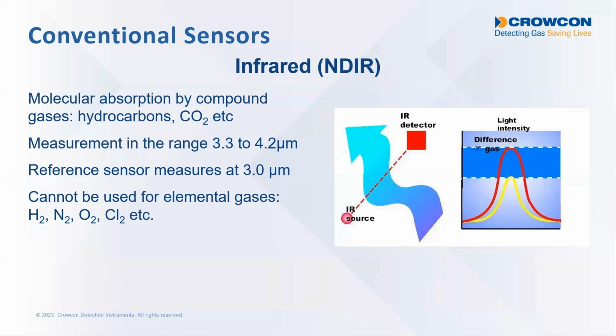Just like the pellistor, we also need to have a reference wavelength so that you can determine absorption of energy due to gas as opposed to absorption of energy due to contamination on the window or the mirror, or perhaps the infrared source starting to fail. So the system is measuring the difference between the two sensors in the detector.